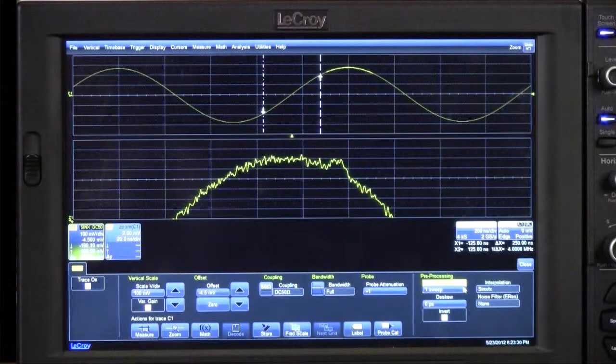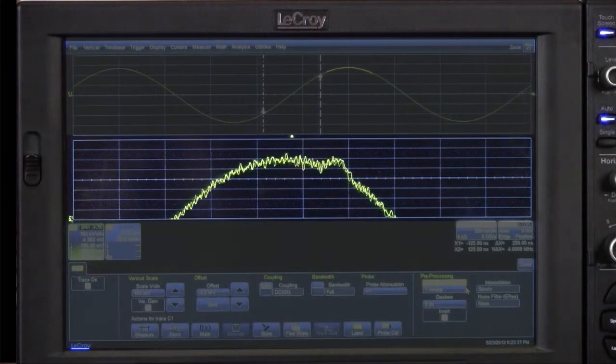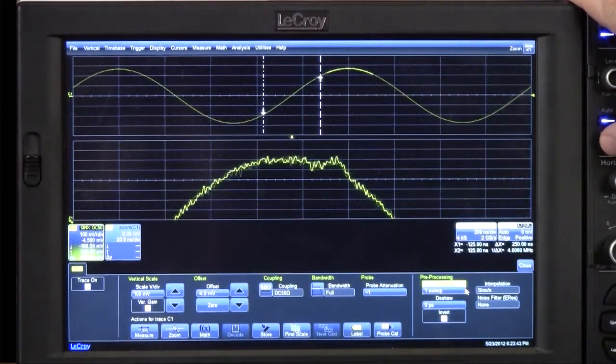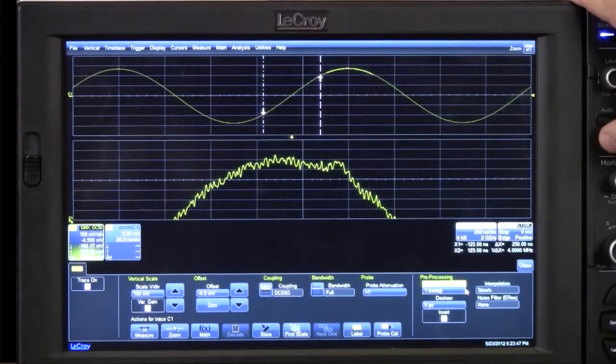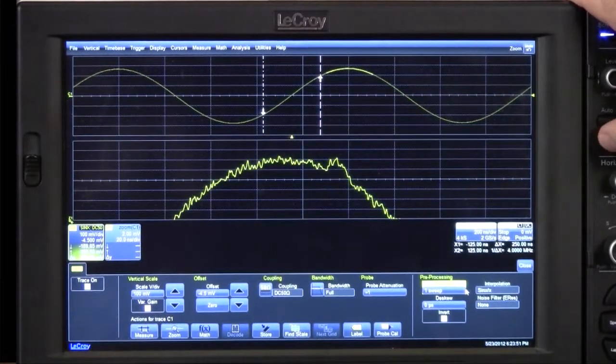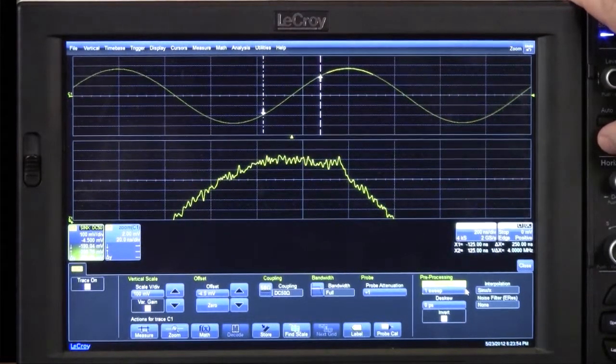Both oscilloscopes are set up identically. At the top of the screen you can see the full sine wave, and then I've created a separate zoom window that shows the small pulse injected on that wave. If I look at the oscilloscope running freely, it's hard to discriminate the attributes associated with that small pulse, and in fact if I do a single run after a single run, it's really impossible to tell any specific characteristics about it.